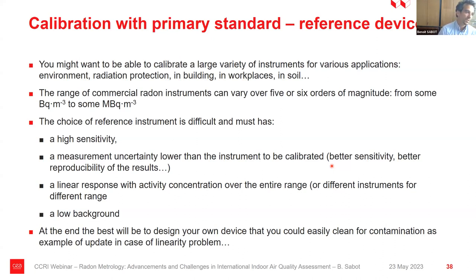So at the end, the important part in this is to select the best reference device you can find, because you may need to have something that has a nice response over a very large range of activity concentration. So it needs a high sensitivity, of course, quite a low measurement uncertainty. The response must be linear with the activity concentration. And if possible, it must have a low background.